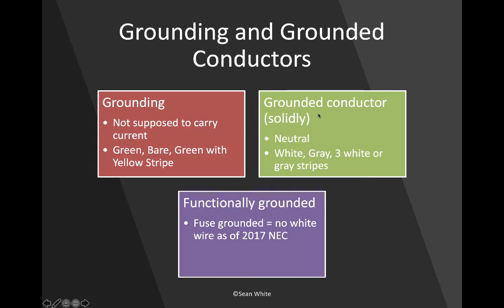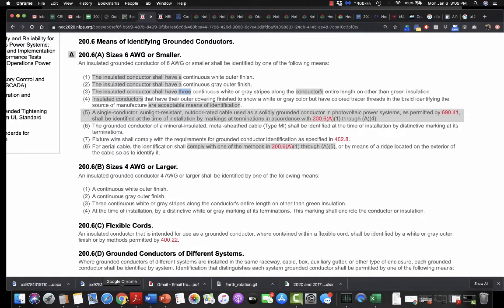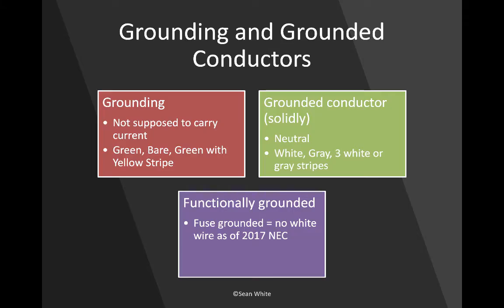On the other hand, we can have a grounded conductor, and let's qualify that as a solidly grounded conductor as opposed to a functionally grounded conductor. A grounded conductor that's solidly grounded, a lot of times we call that a neutral, and that grounded conductor does carry current, and it can be white, gray, or three white stripes or three gray stripes, as we talked about when we were covering Article 200, grounded conductors. Then there is the functionally grounded, which is now the fuse grounded. We talk about functionally grounded with anything that is 2017 NEC and later. Before 2017 NEC, we didn't have functionally grounded.